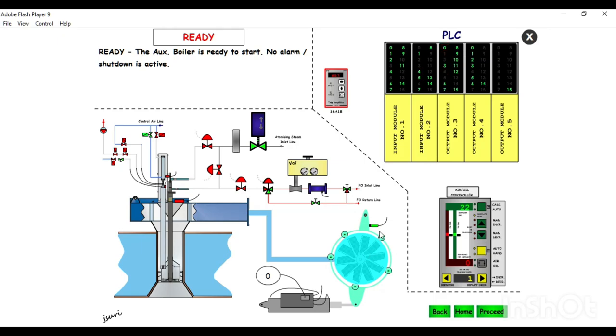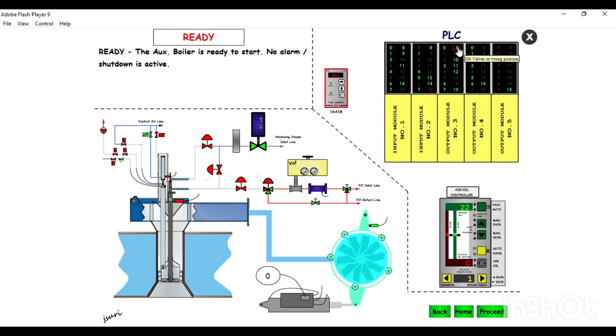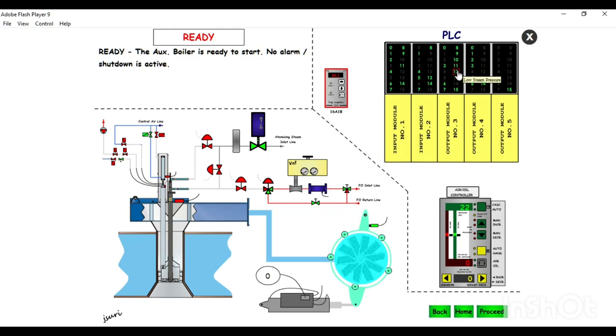In the output module, point zero is for starting the combustion air fan. Point three is for opening the atomizing steam valve - it gets input from field devices and processes the output to open the steam inlet. We also have alarms for oil valves in wrong position, low atomizing pressure, low fuel oil pressure, high fuel oil temperature, and low steam pressure.